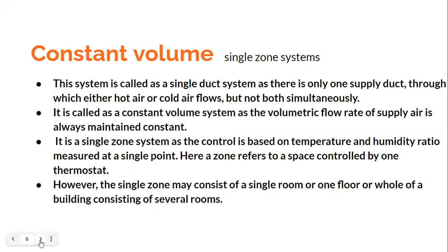But then why do you call it a single zone? Even if there are several rooms, we would call it a single zone if you are maintaining all these rooms at a single temperature and a single humidity. Okay, so that is the way of calling it a zone. So a zone does not necessarily overlap with the room. We might have multiple rooms as a single zone.